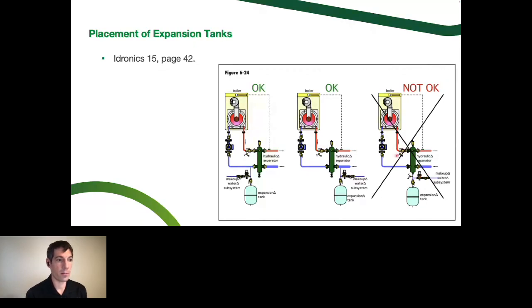The one on the bottom of the separator that I discourage is for a couple different reasons. One, the makeup water is going to go through this vessel and push the debris potentially right back into the circulator and the boiler heat exchanger, which is exactly what we're trying to prevent. Same thing could happen as the system fluid expands and contracts. So as you fire up the system for the first time in the fall for a heating system, and the bladder expands and contracts with the temperature of the water, you could just basically inject all of that dirt right back into the system, which is exactly what we're trying to avoid.